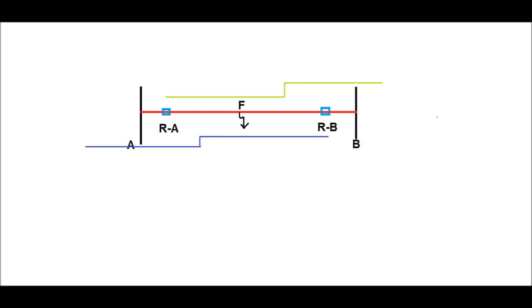Consider a fault occurring at a point F which lies in zone 1 for both the relay at the A end and the relay at the B end simultaneously. Therefore, relay A and relay B trip their respective circuit breakers instantaneously and clear the fault.